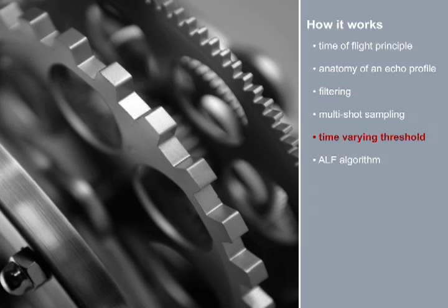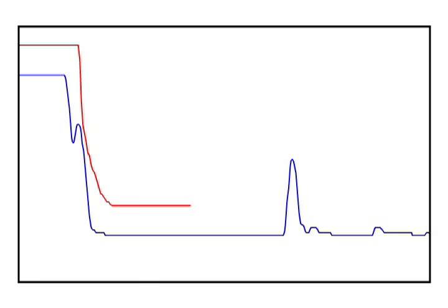TVT, time varying threshold. The dynamic TVT or time varying threshold curve is a mathematically constructed curve to help select the true material echo. The position of the TVT above the echo profile is determined by the height of the echoes above the noise floor.